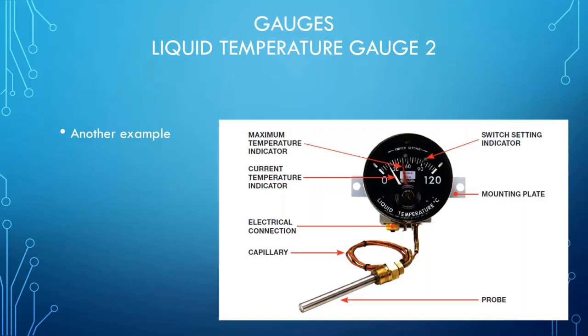Here's another example of a liquid temperature gauge, and this one happens to have switches in it that will close and open contacts based on where the needle is. So this will go back to a PLC or to another device and let someone know remotely that, hey, this transformer is overheating. Someone needs to come inspect it or figure out why it's overloaded, et cetera.